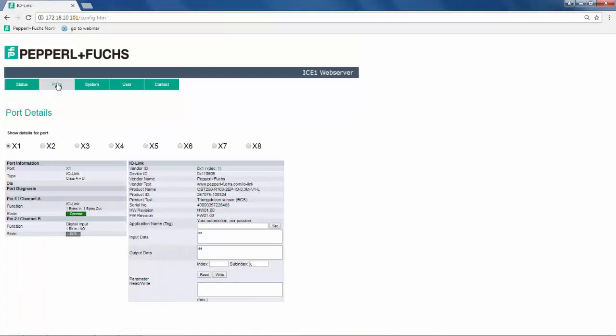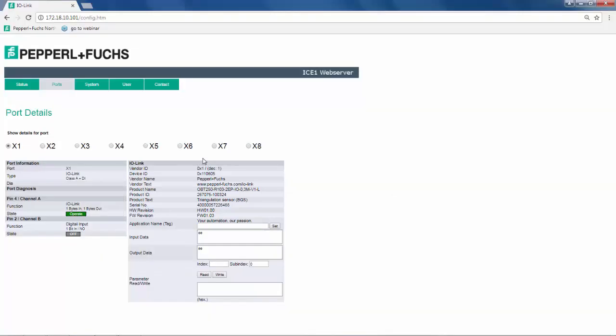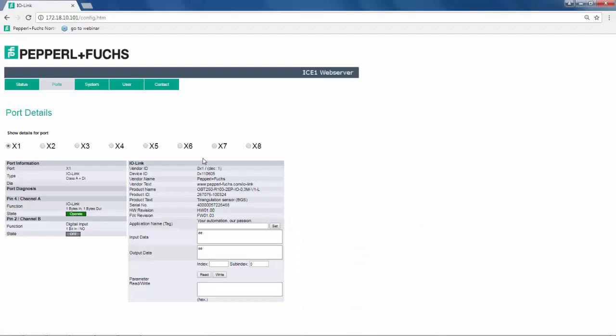Let's move on to the ports page. The ports page enables continuous diagnostics and parameterization down to the sensor and actuator level. In this case, we are monitoring the port details of port 1, which is connected to an R100 sensor. The details of the R100 sensor are noted with the service data located in this area. Right below the service data is the process data. If we interrupt the sensor, we should see our process data changing from a 1 to 0 on the input data.